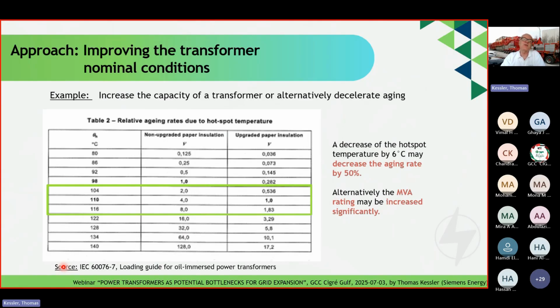There is a table showing the relative aging rates due to hotspot temperature, which looks very statistical, but there is a clear message behind it. If you reduce the hotspot temperature by 6 degrees Celsius or 6 Kelvin - from 116 to 110, or 110 to 104 - you can decrease the aging rate of the paper insulation by 50%.